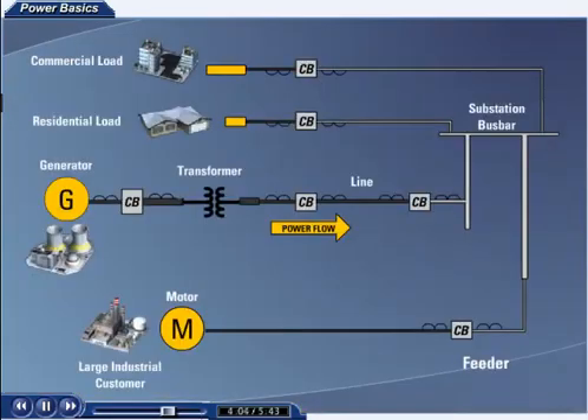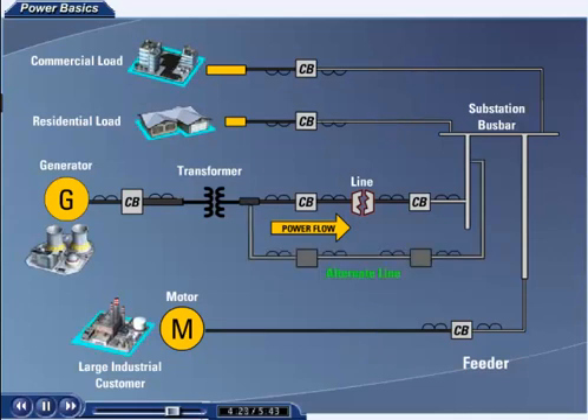The power system can be thought of as a chain, the links of which are the generators, the power transformers, the switchgear, the transmission lines, the distribution circuits, and the loads. The arrangement of these links are as shown. The failure of any link destroys the capacity of the chain to do the work for which it was intended. One way in which the continuity of the chain can be preserved is to provide alternate links. For example, the transmission lines, being exposed to the natural elements, are much more vulnerable to short-circuit faults than the power transformers and switchgear. Hence, alternate transmission lines may be economically justified, whereas alternates for the power transformers and switchgear would not. The network of power systems now blanketing North America are often interconnected at various points to accomplish this.